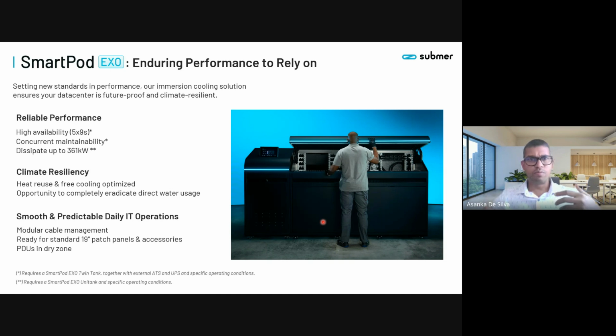And also, once you fix the fault of your server, when you want to immerse the server back into the tank, the fluid level will increase. Now with the buffer tank, the extra fluid will flow to the buffer tank, and it will normalize the right level of fluid. So these little things, which haven't been in previous versions of tanks, have been well thought out, just to make sure that when you deploy an immersion cooling solution at scale, it's easy to maintain and easy to operate.